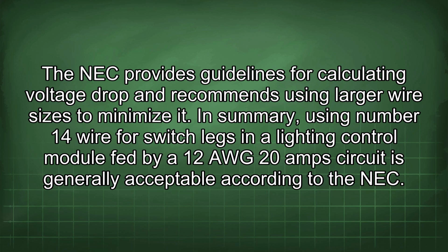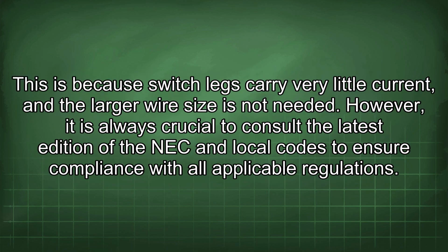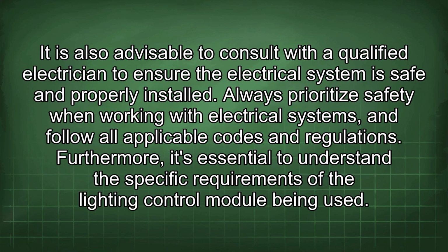In summary, using number 14 wire for switch legs in a lighting control module fed by a 12 AWG 20 amp circuit is generally acceptable according to the NEC. This is because switch legs carry very little current, and the larger wire size is not needed. However, it is always crucial to consult the latest edition of the NEC and local codes to ensure compliance with all applicable regulations. It is also advisable to consult with a qualified electrician to ensure the electrical system is safe and properly installed. Always prioritize safety when working with electrical systems, and follow all applicable codes and regulations.